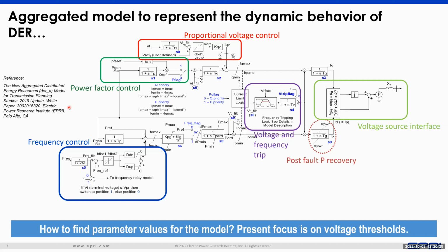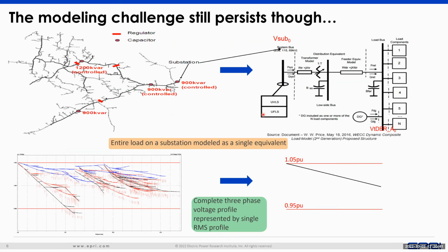The most crucial part of this model is its ability to represent partial tripping of DER across the network. This partial tripping is important because, as we saw in this slide, there's a spread of voltage across the entire network - you have the substation voltage here, and as you go deeper into the network, the voltage spreads out in this manner.